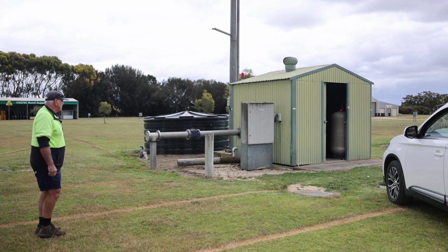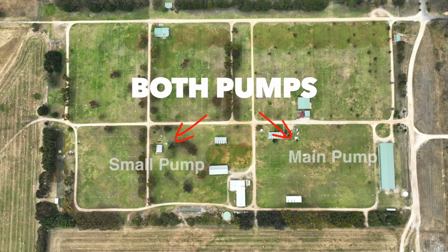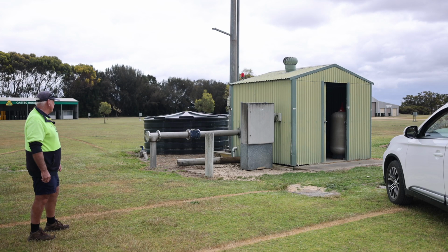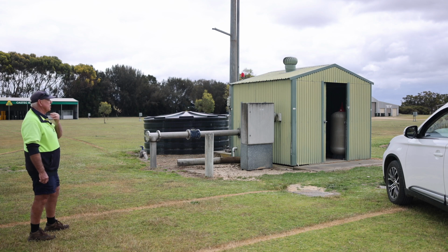Other points here are that there's an interconnect cable going from this bigger pump down to the smaller pump shed. There is a Cat 5 cable in there, and also a twin. The Cat 5 cable was in case we ever put some other telemetry with it, digital telemetry. At the other end there are interfacing relays, and virtually the green pair and the blue pair and mates are joined together, and the brown and green colours and mates are joined together. So it's just 2 wire.